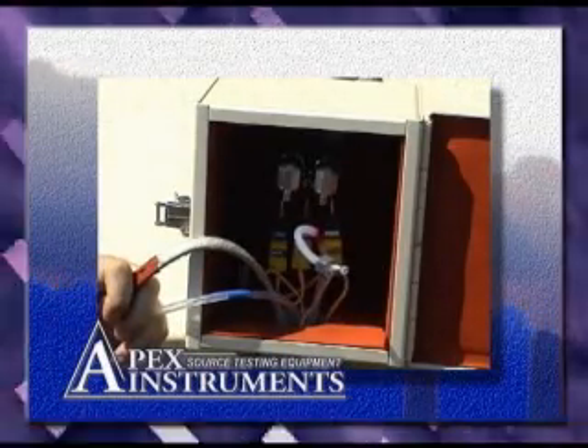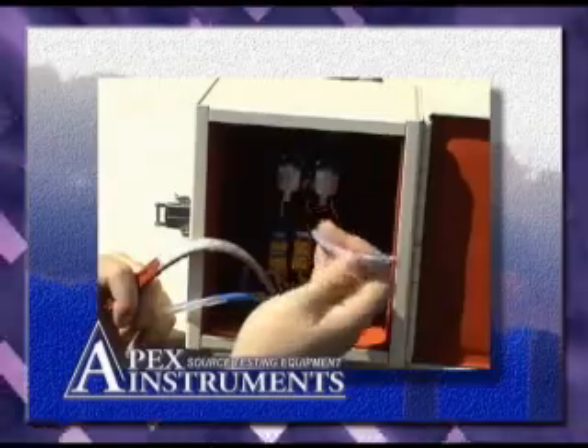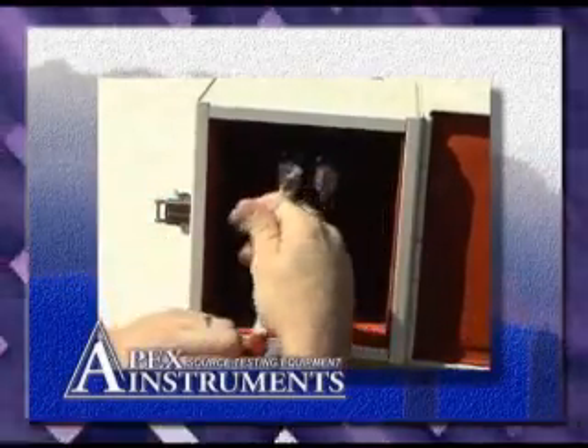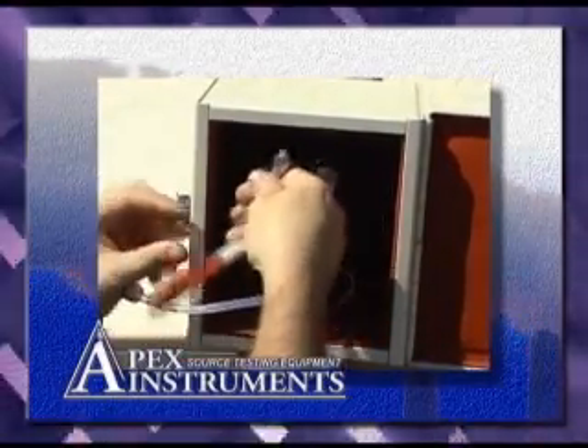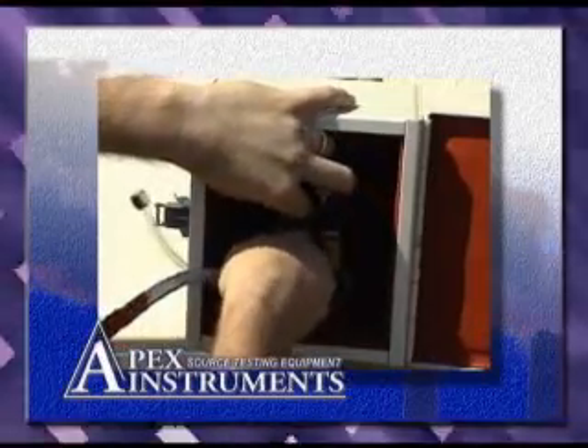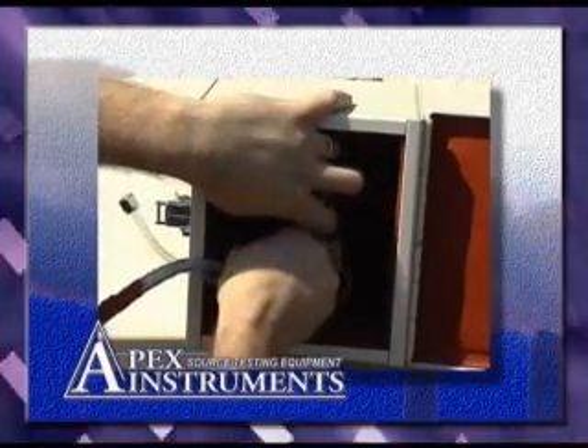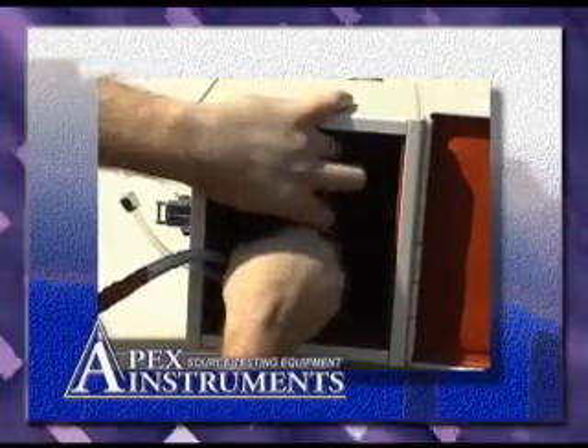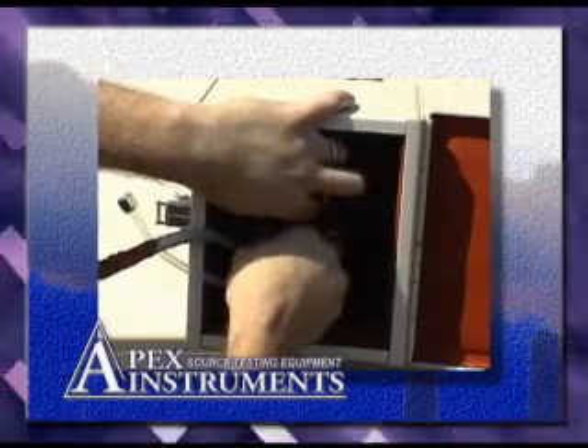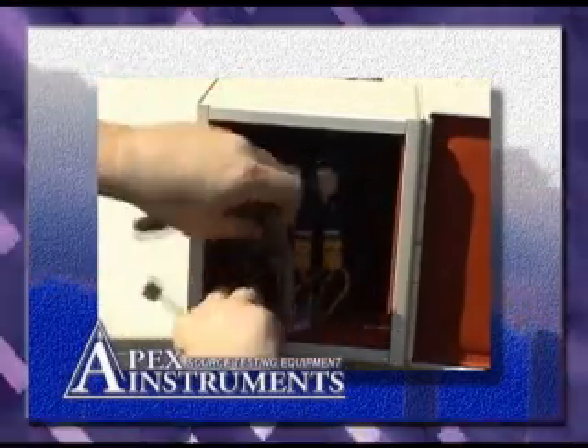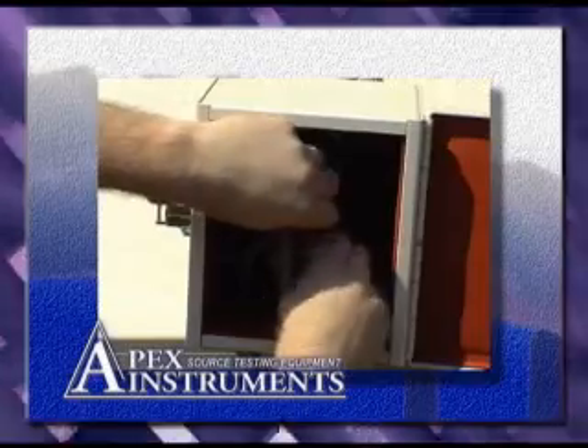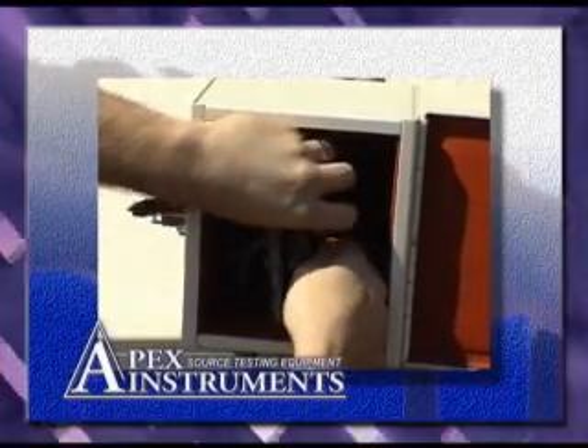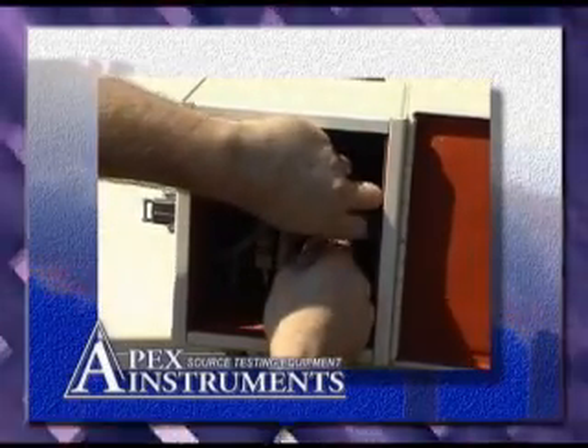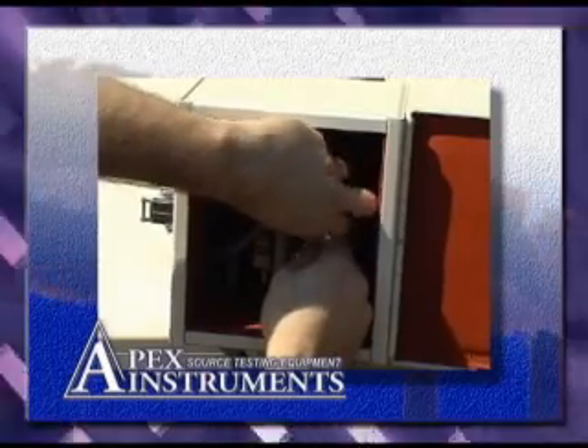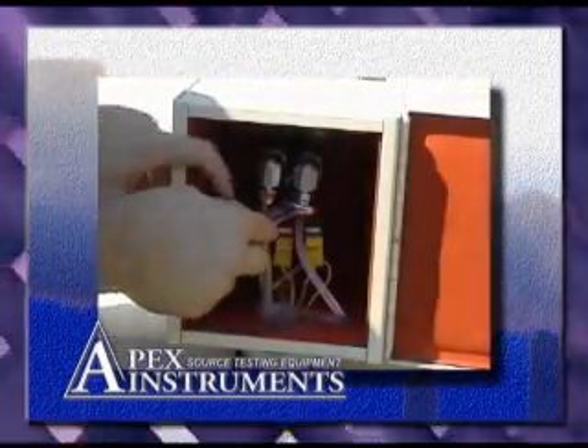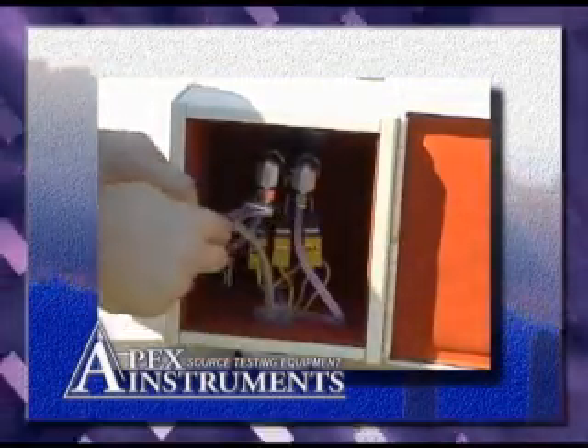Once the thermocouple connections are complete, connect the sample lines. The two sample lines are color-coded to differentiate between them. The A train sample line is color-coded red, and the B train sample line is color-coded blue. These connections should be finger-tightened, then tightened to provide a leak-tight connection using a wrench.